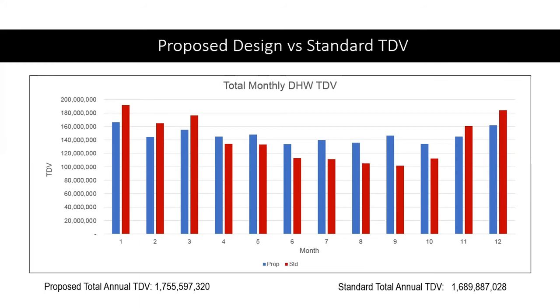So what we're seeing is basically it's saying using electricity during the summer gives you a high TDV impact, even though the actual electricity consumption will be much lower in the summer. Like the system will be way more efficient because it's warmer. Yeah. But the TDV impact, because it's compared to gas, looks bad. Yes, for most of the year even, which is okay. So comparing electric to gas does make it look like there's more electricity being used, because there is.